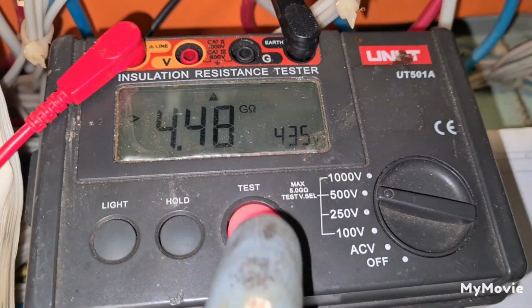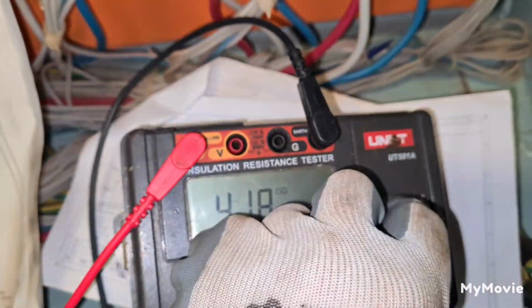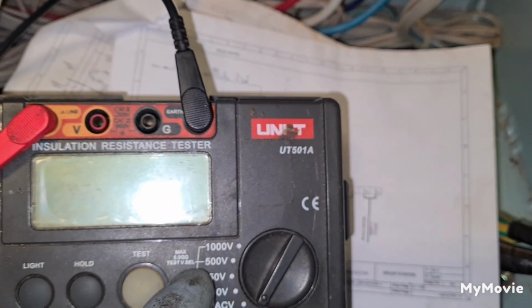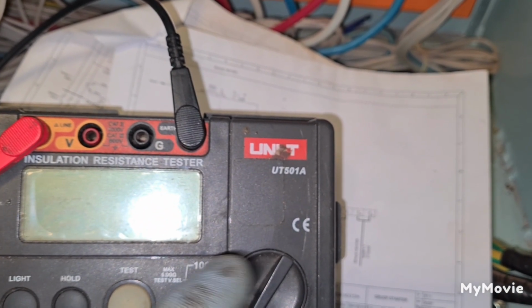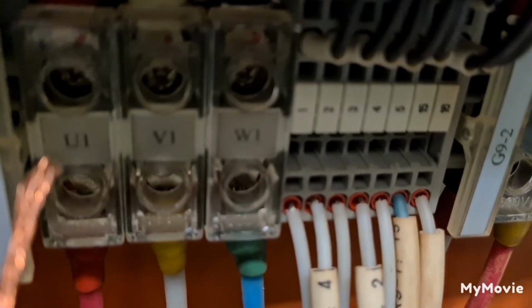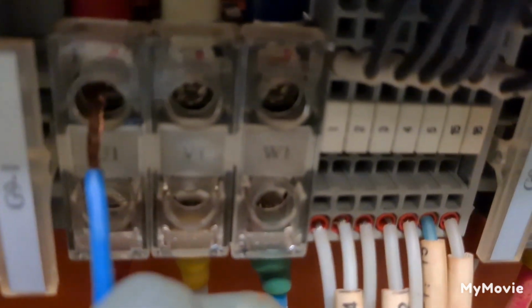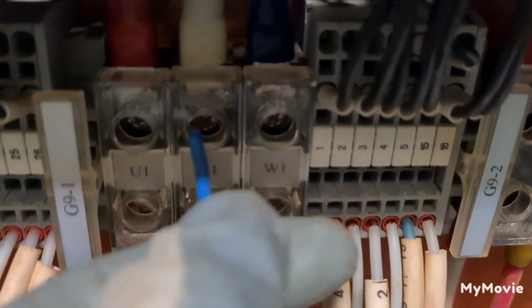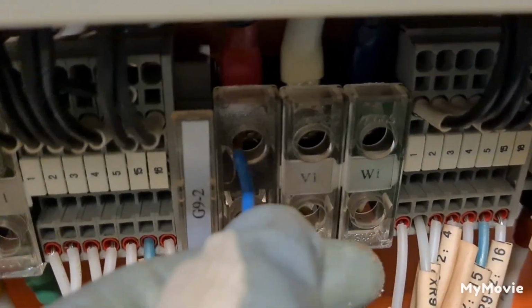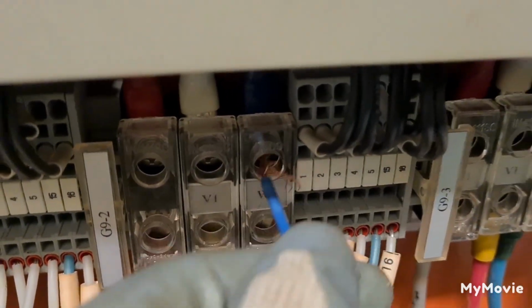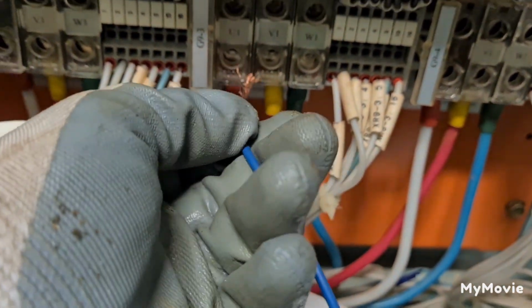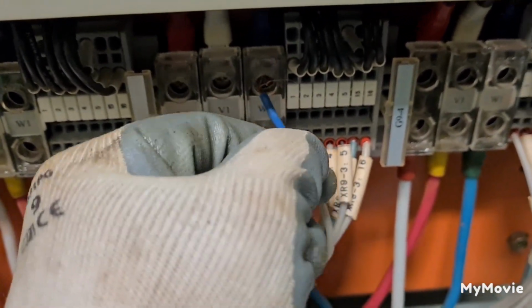So, after you finish, you must depress this one, and then you need to disconnect this one, and then switch off this one. Okay? Normally, when you have motors which are working at 450 volts, you can use 500 volts to 1000 volts. Okay. So after doing the insulation test, we must short line to ground, so you can remove the residual voltage that you applied on the motor. So I just connect this to the ground wire, and I will be able to remove the residual voltage on the motor.